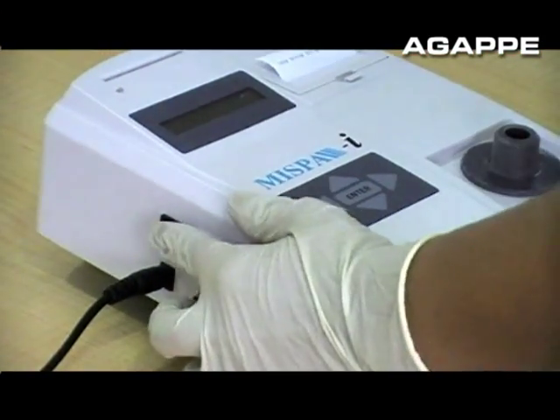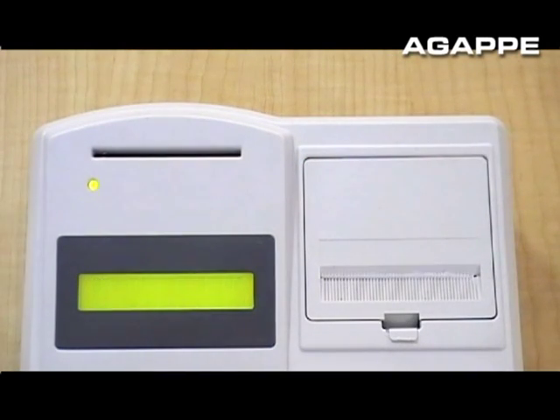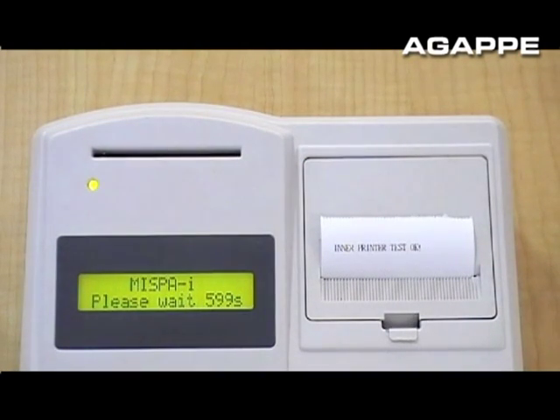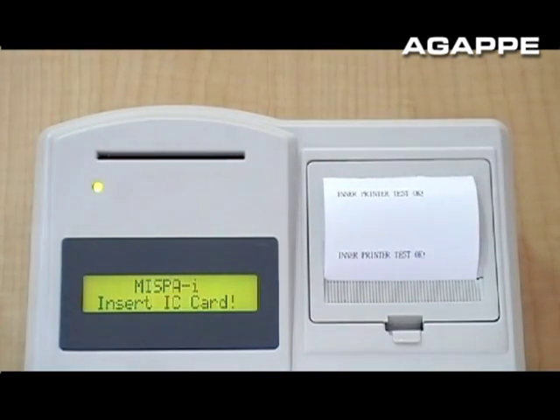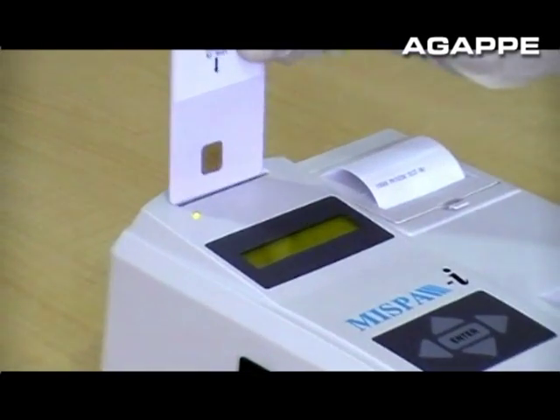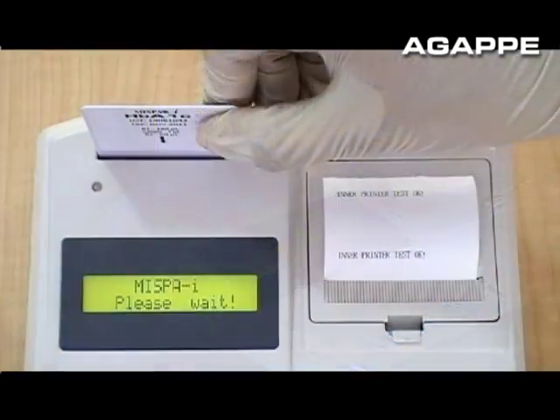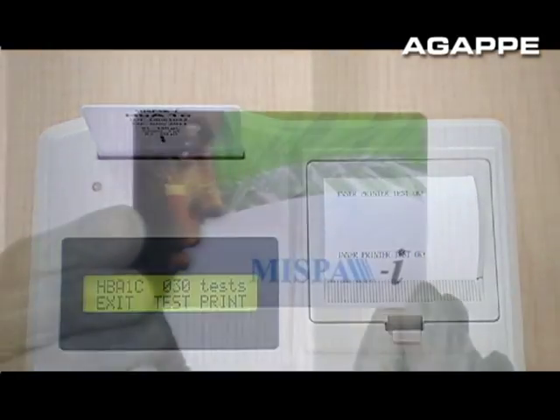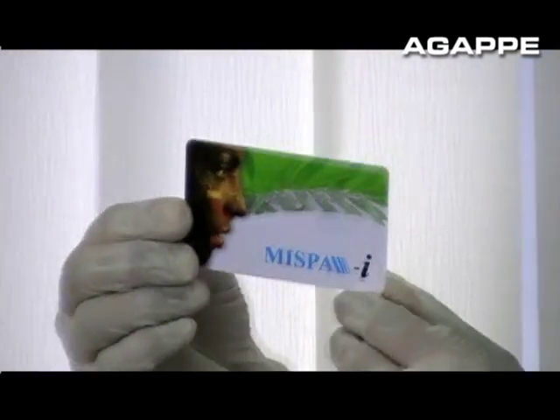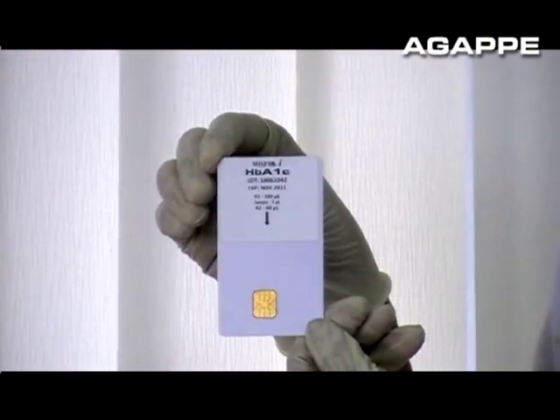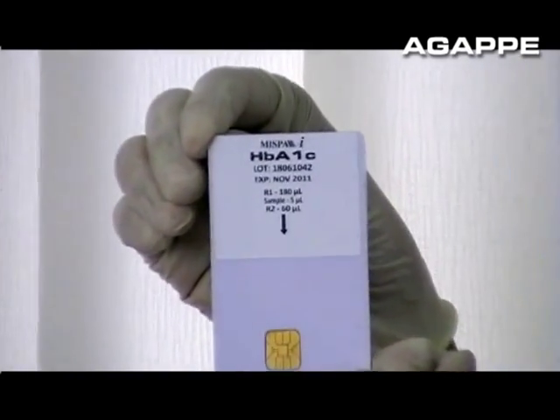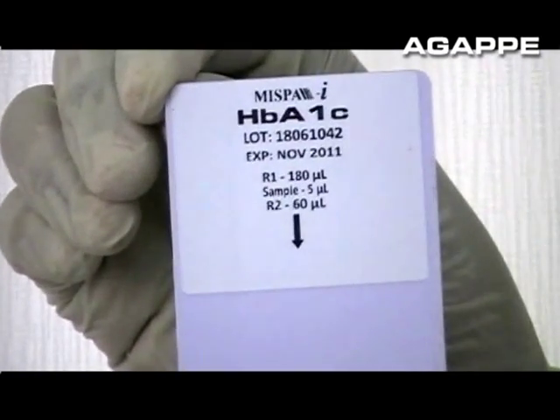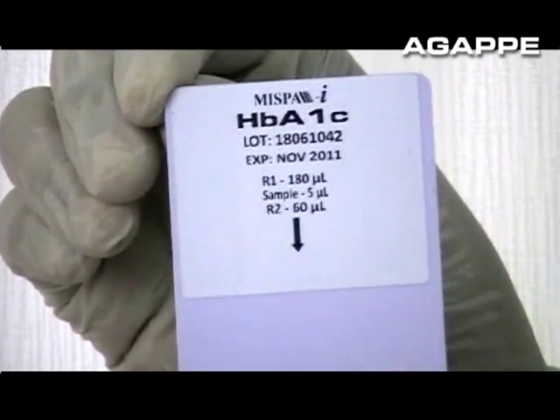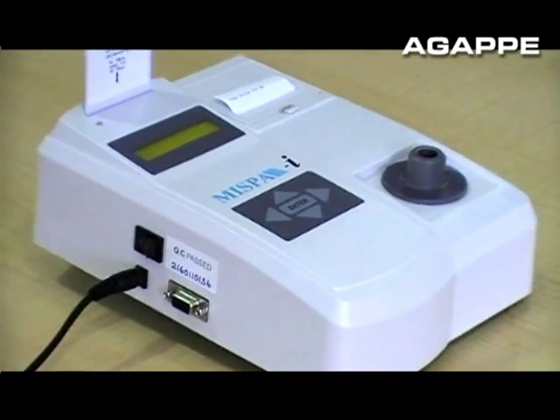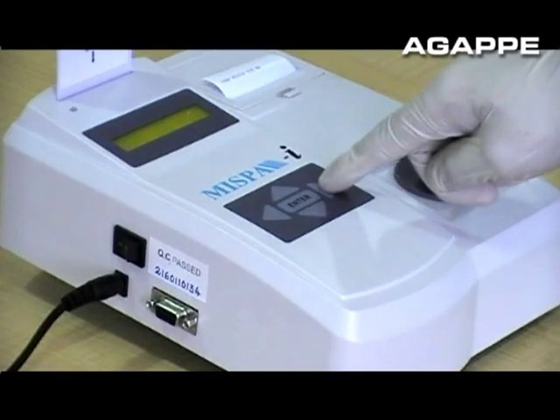Turn the power on. MISPA-i will take 10 minutes to warm up. This will happen only at the time of power up. Calibrating MISPA-i is very easy. Just insert the IC card. The calibration will happen automatically. This multi-point calibration guarantees accurate results. Reaction volume, expiry details, and lot number information are also included with the IC card. This avoids the extra requirement of a kit insert. If you want, you can print the test details by simply pressing the right button.